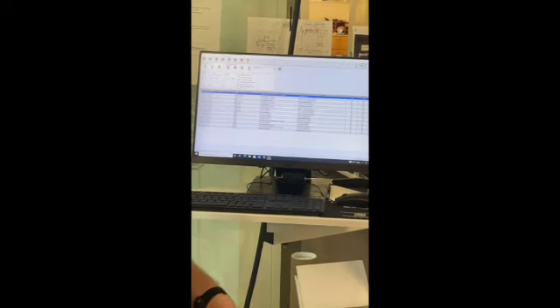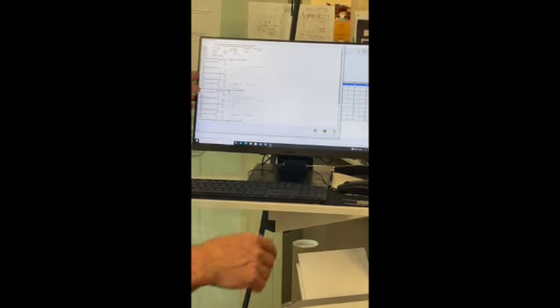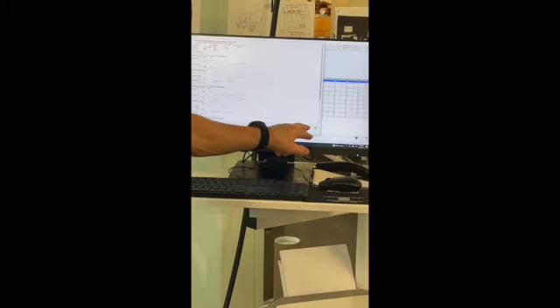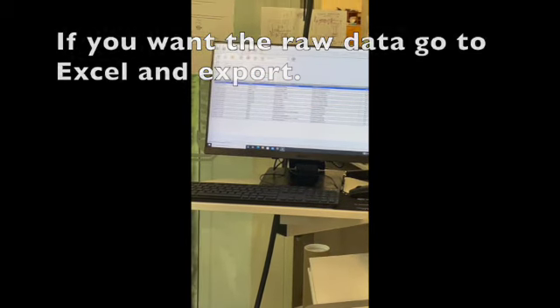When all done and you confirm, the data is saved. For an isometric protocol, the available reports are isometric-specific; isokinetics have a broader set of reports. If you click Preview, you'll see peak torque, average torque, slope, halftime, and time to peak torque. If you want the raw time-series data, click Excel — that dumps out the raw data. You can also stream data out the auxiliary outputs simultaneously while collecting inside the HUMAC, giving you both raw and calculated data.